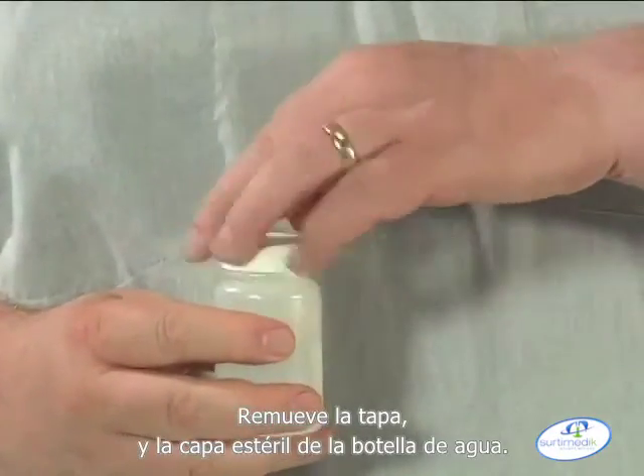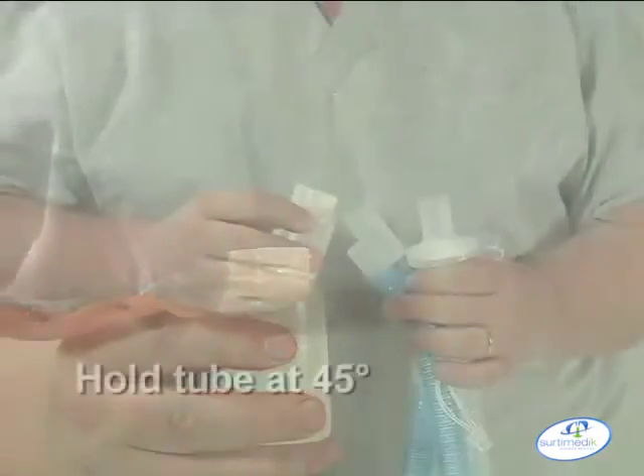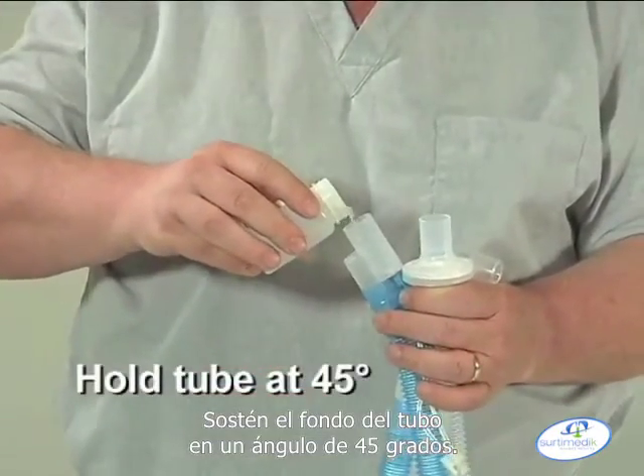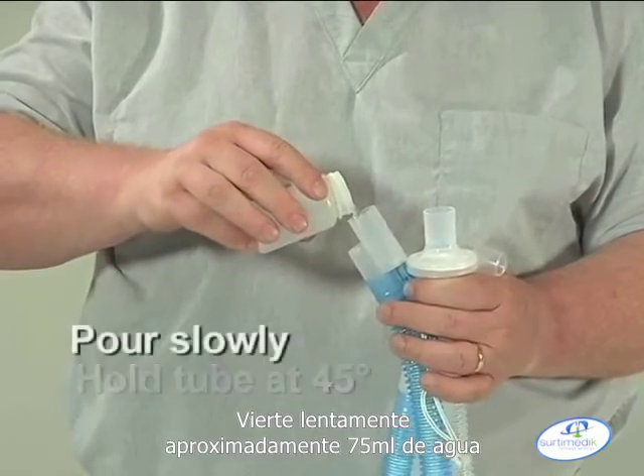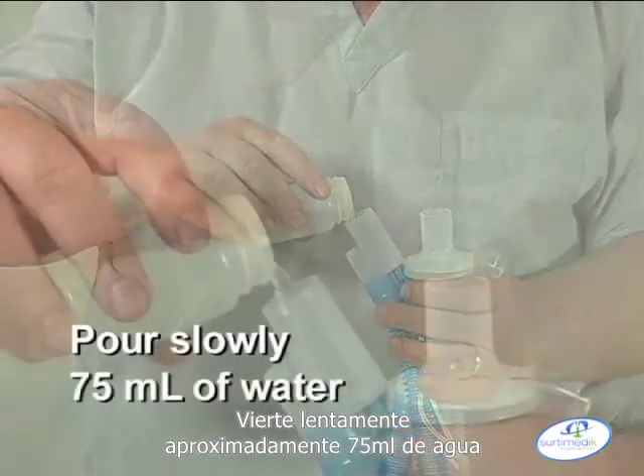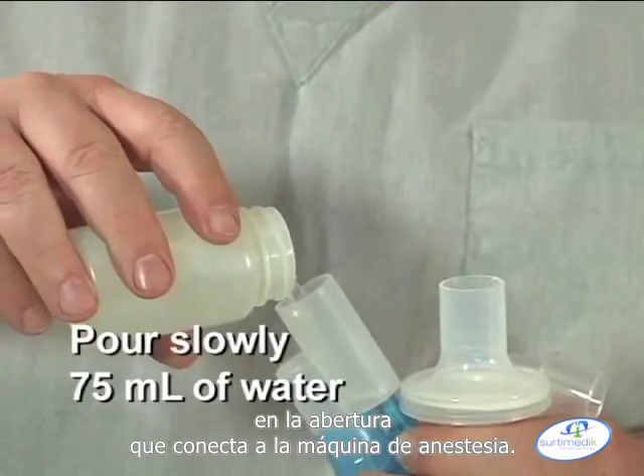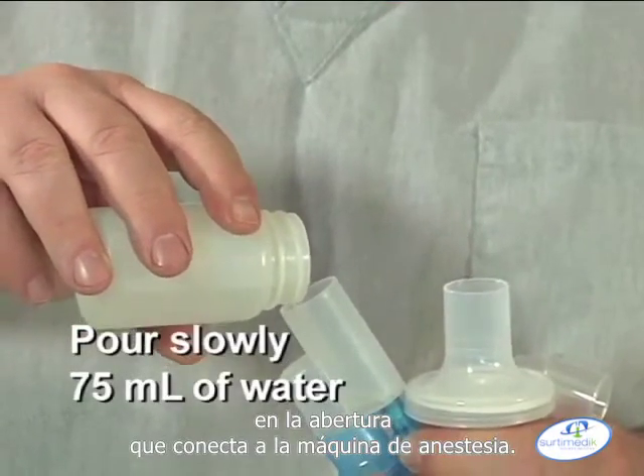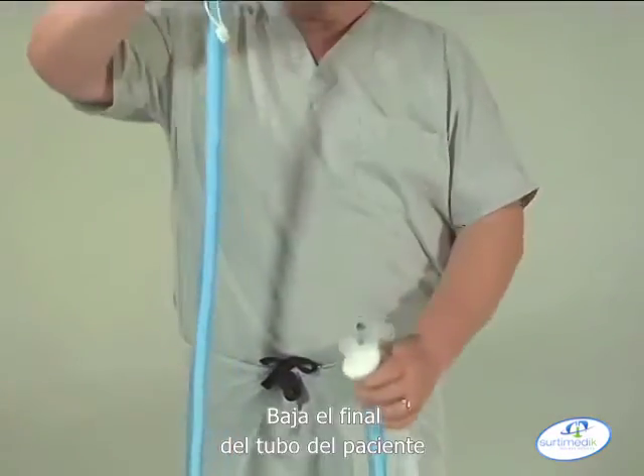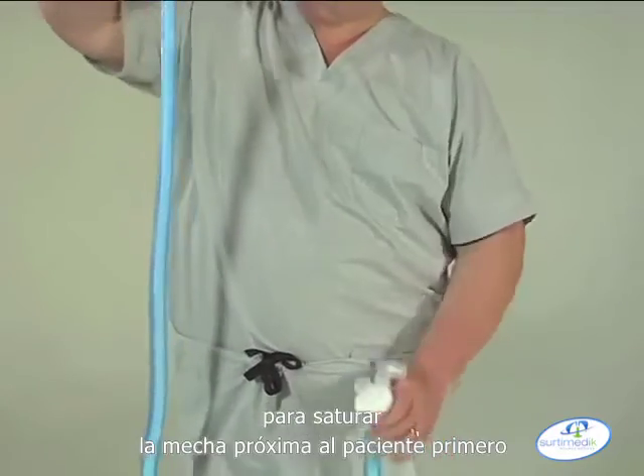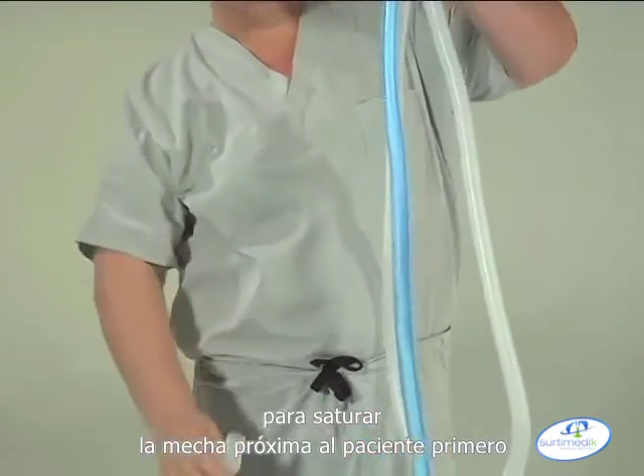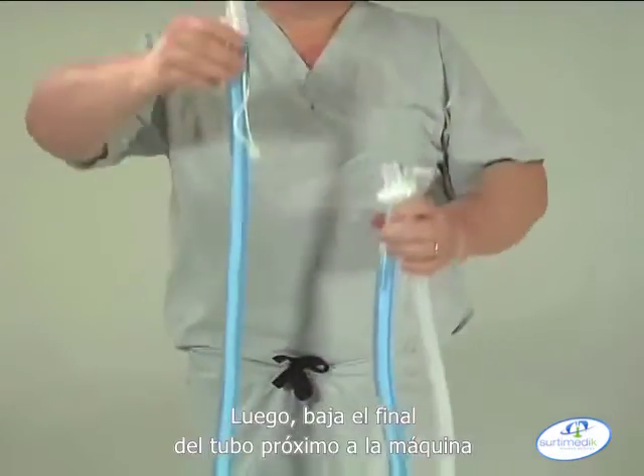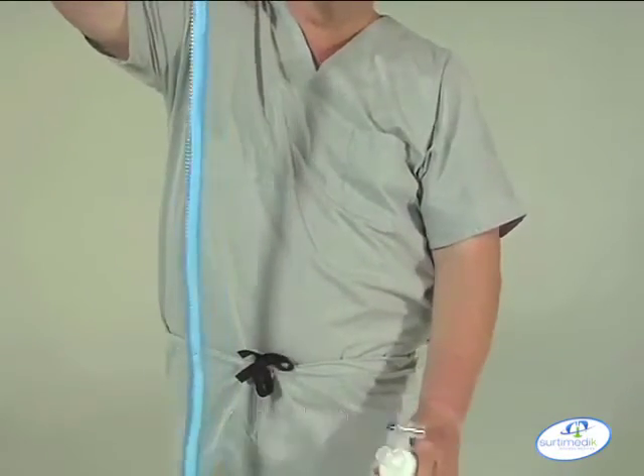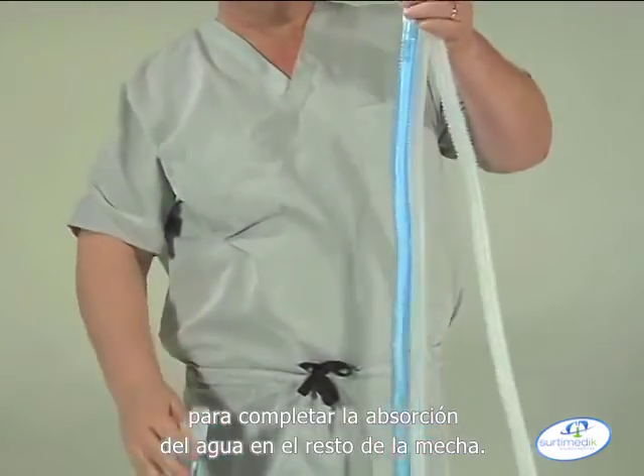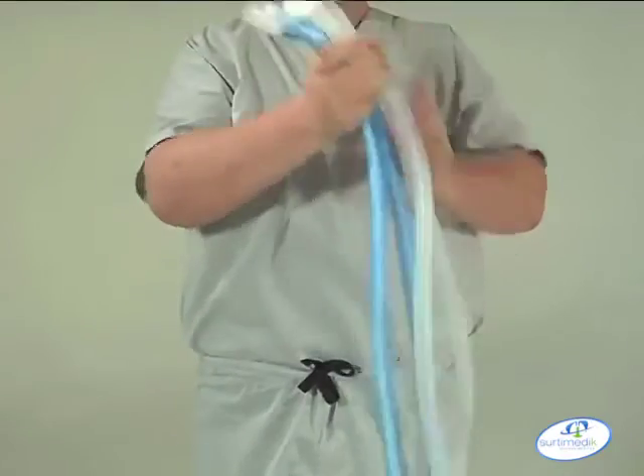Remove screw cap and sterile cover from water bottle. Hold the end of the tube at a 45-degree angle. Pour slowly approximately 75 milliliters of water into the opening that connects to the anesthesia machine. Lower the patient end of the tube to saturate the wick of the patient end first. Then, lower the machine end of the tube to complete the absorption of the water into the wick material.